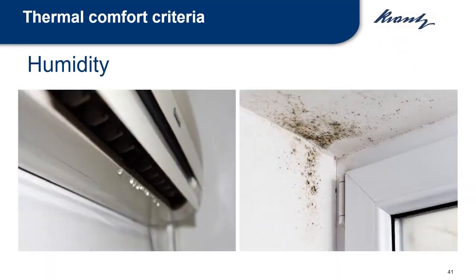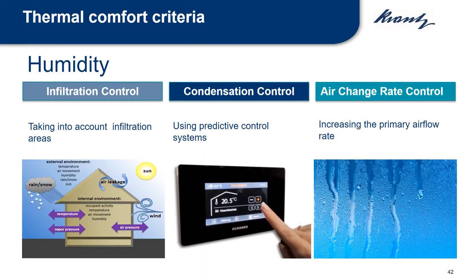We all know what an excess of moisture can cause in buildings, in cooling systems, especially in hot countries, and in air quality: the accumulation of fungus and bacteria, among other things. But how can a good air distribution system control or avoid such moisture? Taking into account infiltration areas like the entrance of buildings, open windows, the spaces between floors, where people accumulate, etc., it becomes necessary to be aware of the infiltration points. To use predictive control systems to control and prevent the accumulation of local humidity, or even to increase the primary airflow rate to avoid condensation processes.